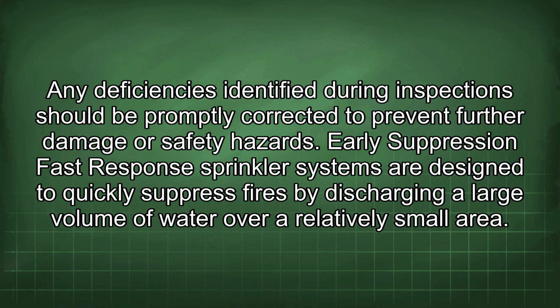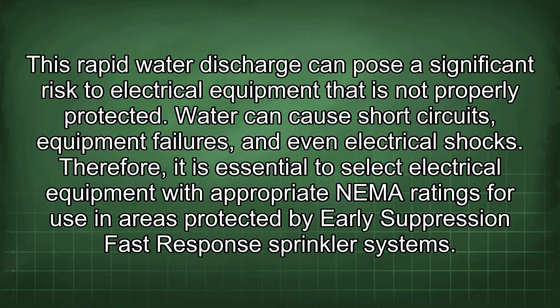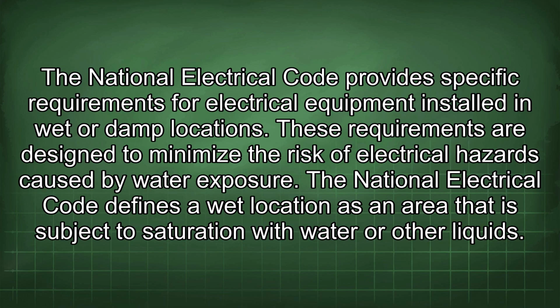Early suppression fast response sprinkler systems are designed to quickly suppress fires by discharging a large volume of water over a relatively small area. This rapid water discharge can pose a significant risk to electrical equipment that is not properly protected. Water can cause short circuits, equipment failures, and even electrical shocks. Therefore, it is essential to select electrical equipment with appropriate NEMA ratings for use in areas protected by early suppression fast response sprinkler systems. The National Electrical Code provides specific requirements for electrical equipment installed in wet or damp locations. These requirements are designed to minimize the risk of electrical hazards caused by water exposure.